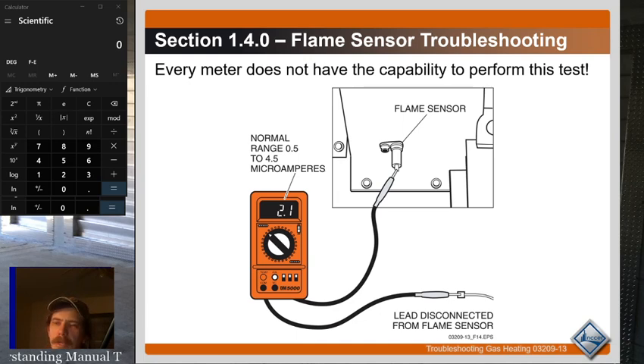to verify the flame signal, and that's such a small reading that any problems in that flame sensor circuit can make it not work properly. So generally a flame sensor, if you clean it, it'll work just fine, but if it doesn't, then you need to verify whether the issue is the flame sensor or something else. So the normal range is 0.5 to 4.5 microamps, okay? And you test that in line. So if you've never checked amperage without using an amp clamp, but by checking it through the meter, this is how you check amperage through a meter.